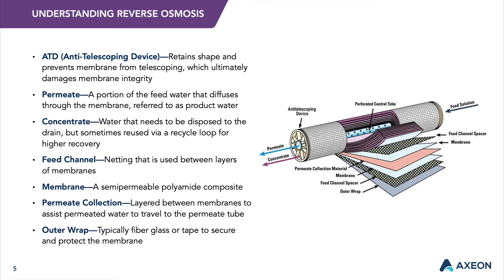Membrane elements contain from 1 to more than 30 membrane leaves depending on the element diameter and element type. Each leaf is made of two membrane sheets glued together back-to-back, with a permeate spacer between them. A semi-automated process produces consistent glue lines of about 1.5 inches or 4 centimeters wide that seal the inner permeate side of the leaf against the outer feed concentrate side. There is a side glue line at the feed end and at the concentrate end of the element, and a closing glue line at the outer diameter of the element. The open side of the leaf is connected to and sealed against the perforated central part of the water tube, which collects the permeate from all leaves. The leaves are rolled up with a sheet of feed spacer between each of them, which provides the channel for the feed and concentrate flow.